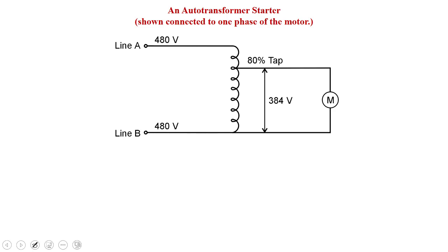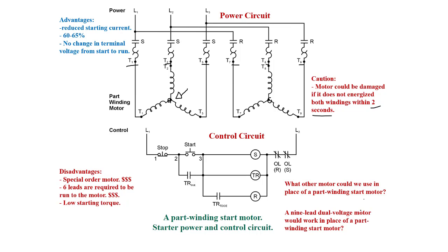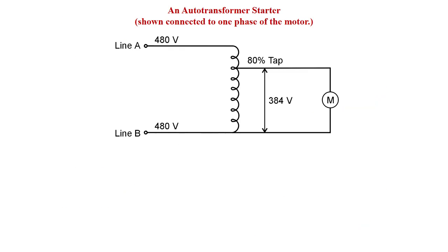Okay, the next one we're going to look at here is auto transformer starters. For this one, we're just going to look at a single phase motor, and here's what it would look like. You recall auto transformers from when we studied them. We have basically a tap coming off at different points, and that will give us a different voltage. So we're going to use these as step down auto transformers.